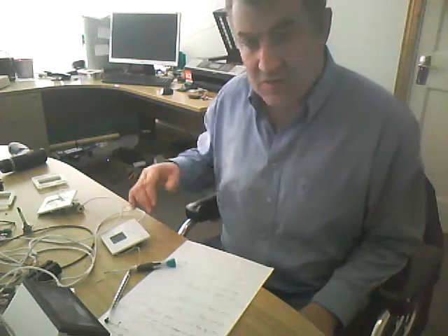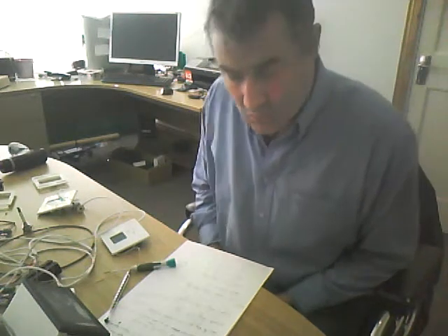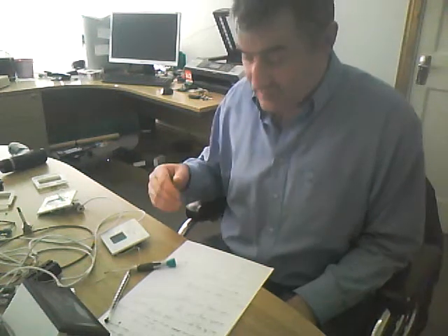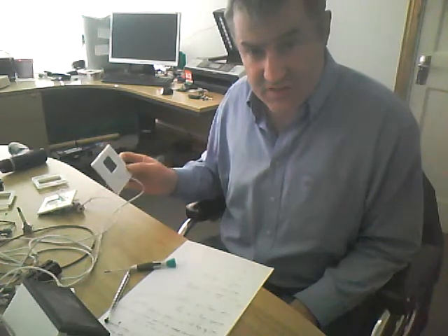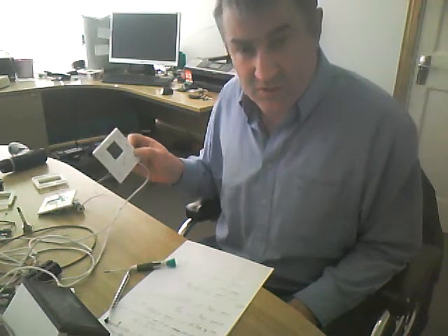Okay. Your fourth step, you would go and you would select the relay that you want to be activated using this differential setup. So in my particular case, I went to logic box 6, relay number 1. The activation used to turn that on then is their differential. And the differential used is in relation to the domestic hot water. Our first one here we set up as domestic hot water was zone 5.